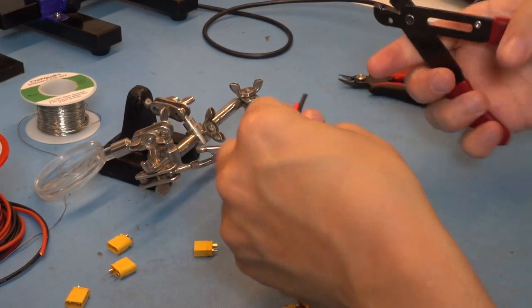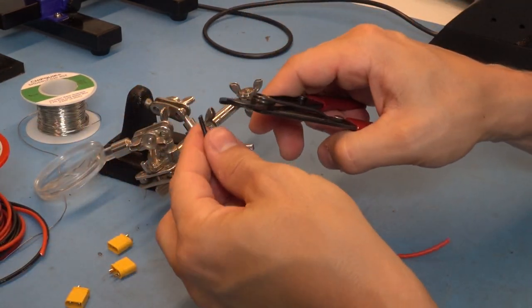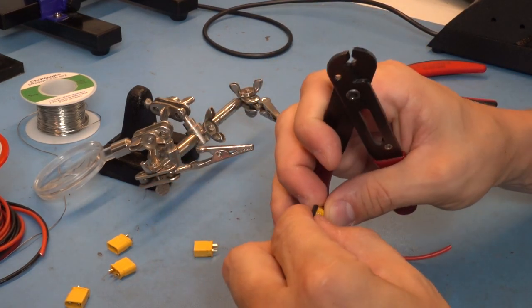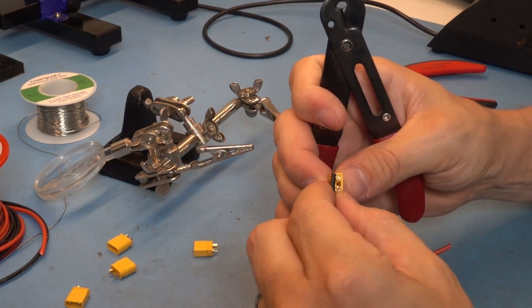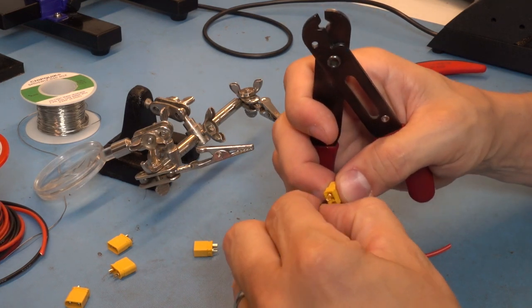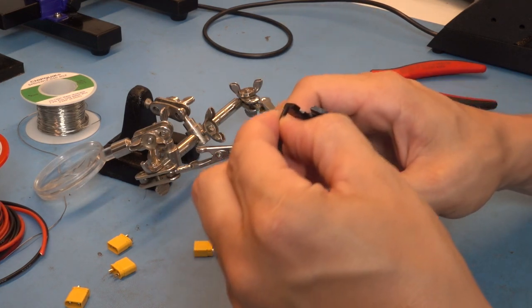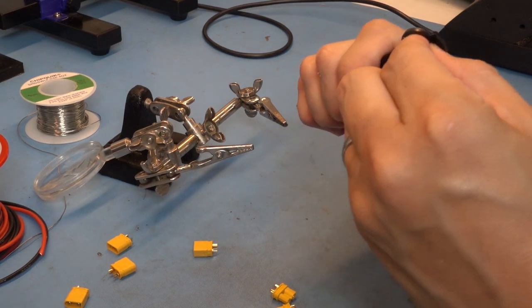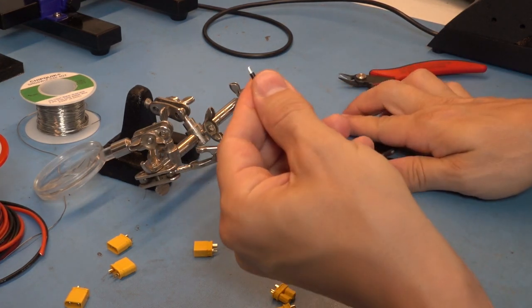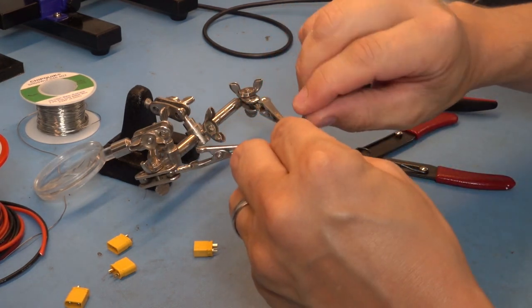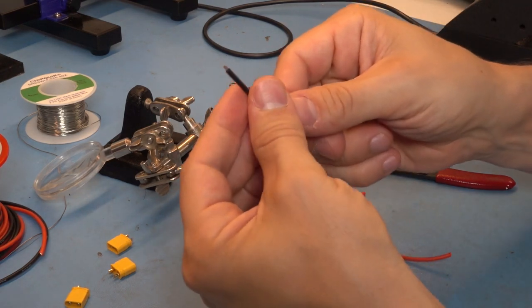Then I'll strip each of these. You want to remove about as much as the length of the terminal—that's maybe two or three millimeters. Try not to nick any of the strands, or at least as few as you can.